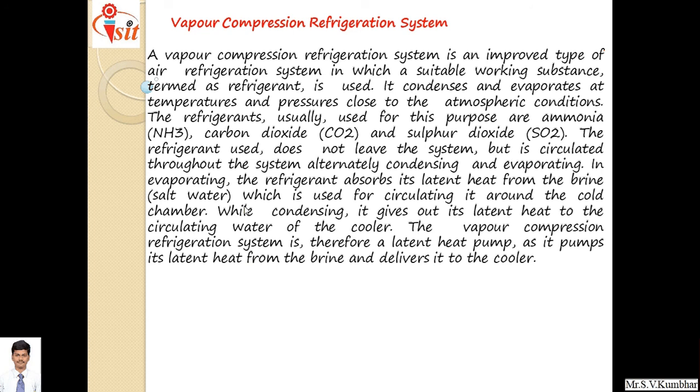It condenses and evaporates at a temperature and pressure close to the atmospheric condition. The refrigerants usually used for this purpose are ammonia, carbon dioxide, sulfur dioxide. Nowadays, we are using R134a as refrigerant in refrigeration. The refrigerant used does not leave the system, so it acts as a closed system, but it is circulated throughout the system, alternately condensing and evaporating.